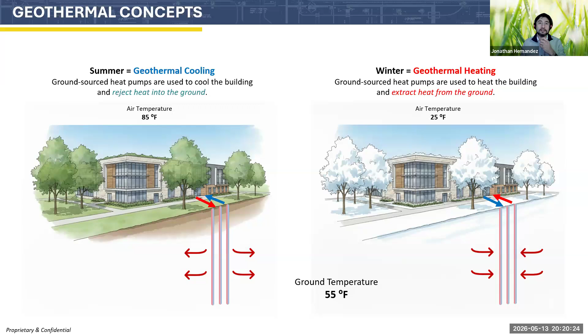But overall, you're using this. You're exploiting thermal conductivity through a solid, essentially heat transfer through a solid, using conduction. And that's what the high-density polyethylene pipes are, loops set within thermally enhanced grout. Now, you'll notice that thermal conductivity is an efficiency rate. It doesn't measure the actual capacity of the system. It just tells you how fast heat can be transferred in and out of that particular borehole.